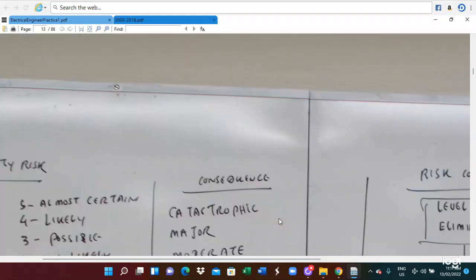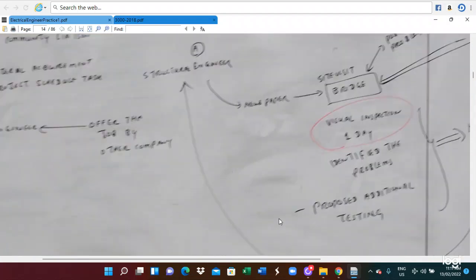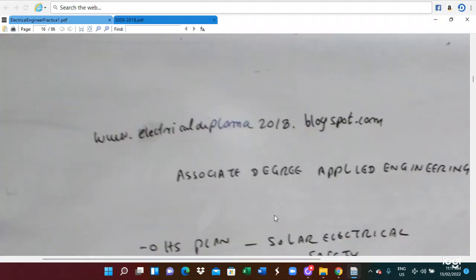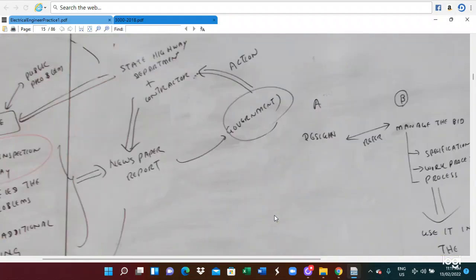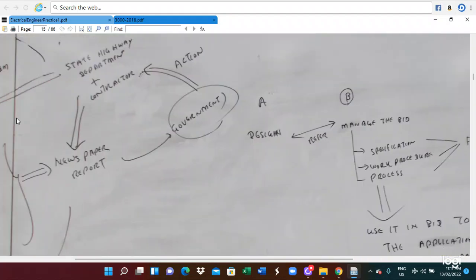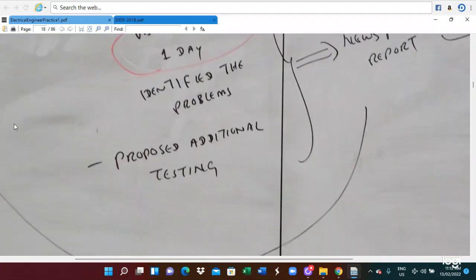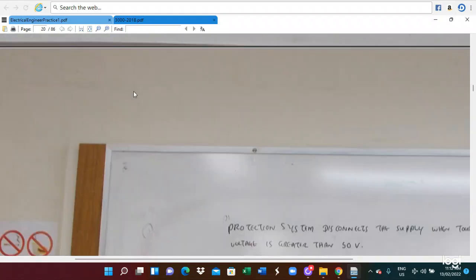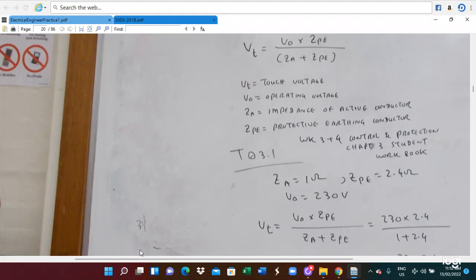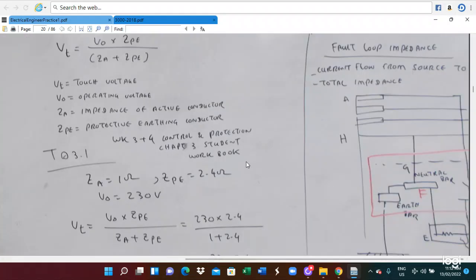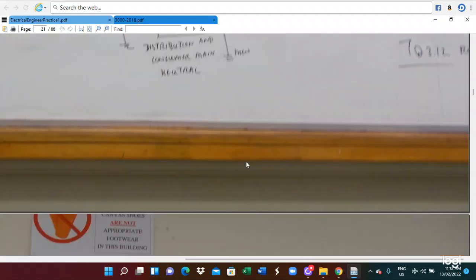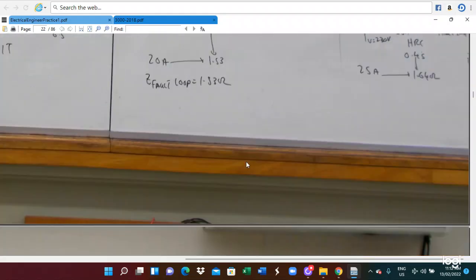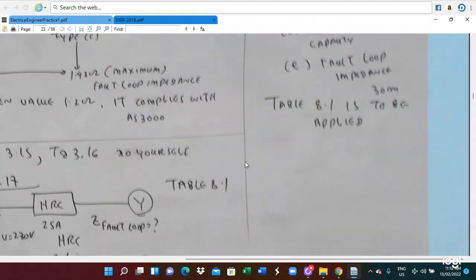And I also talk about risk assessment data. And then an important topic is the contract procedure: contract bidding and ethical practice, which I explain. And then I talk about the protection system. Because you are doing the electrical system, the protective device is an important aspect. I talk about fault loop impedance and the fault loop impedance calculation, also the protective device rating. We talk about how to apply the AS3000 rules, how to refer to the tables, how to select the current and circuit configuration. This is for the electrical engineer aspects.